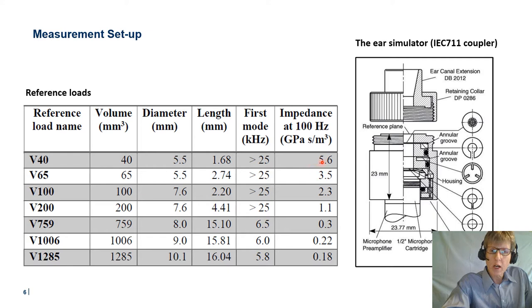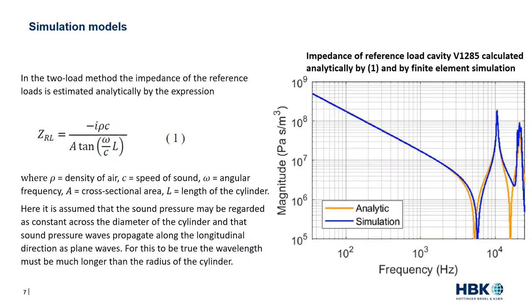As an example of a more complex load, we have the IEC711 coupler, with a measurement microphone, a 12.5 millimeter ear canal extension, and narrow slits leading to two annular cavities.